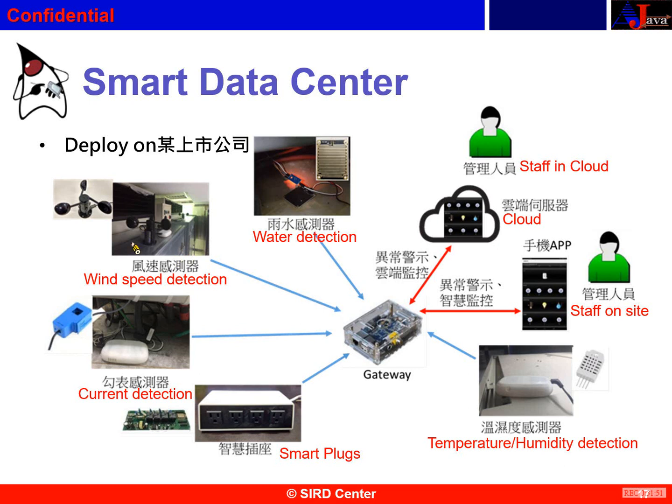All the information, the temperature, the humidity and the fan speed, is collected, so you can say maybe this fan is going down, because you can see the fluctuation. We can also detect how much power you consume, so if there is fluctuation in your power usage, the machine needs maintenance.